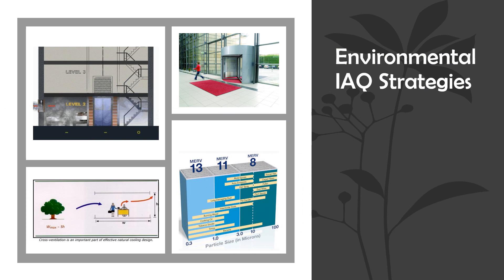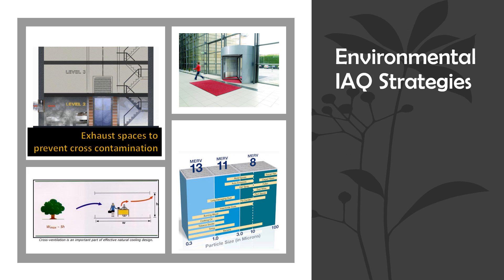What are the strategies? First, you can install entryway systems that are at least 10 feet long to capture dirt entering the buildings. Second, you can exhaust each space where there are hazardous gases — like garages and copier rooms — by creating a negative pressure between those spaces and the surrounding spaces.